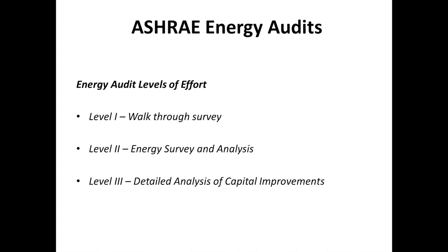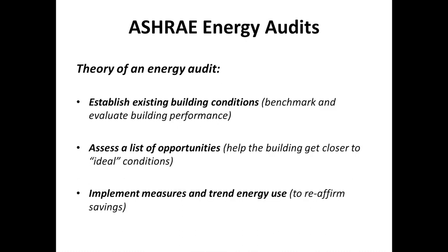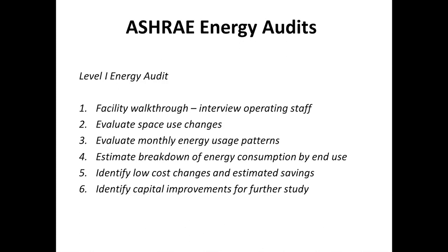There's 3 basic levels of energy audits under ASHRAE. Level 1 is really a walkthrough survey. So again, this slide is just showing the theory of an energy audit. I'm going to go through the levels in a minute. But it's really to establish building conditions, benchmark and evaluate how the building's performing, and assess the list of opportunities based on the performance of the building, assuming that your building's not perfect, which very few, if any, are, and then also implement recommended measures and track energy use.